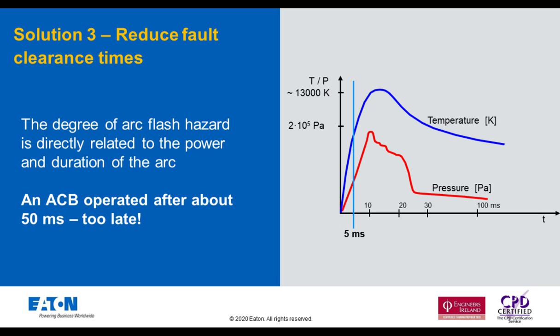Eaton also have some patented technology called ARMS, which is employed on both their ACBs and their newly launched PXR moulded case circuit breakers. ARMS stands for Arc Flash Reduction Maintenance System. Once the ARMS device is activated, the 50 milliseconds of operation is typically reduced to about half. Again, this reduces the amount of arc energy further, and reduces the risks to personnel and damage to the assembly.